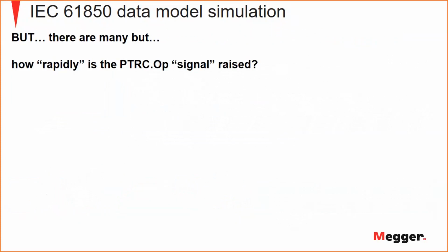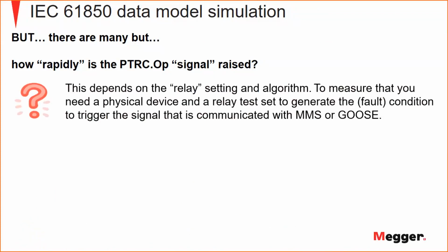But I am a relay protection engineer and I have some issues here. I have my relay protection, I have my settings of my timers, I have my configuration. The relay can be blocked, it can be unblocked, it can be accelerated by carrier send, carrier receive signals, whatever. So I want to see that, and this cannot be done. How fast is a PTRC op signal, so the trip signal, raised? This depends, of course, on the relay setting and the relay algorithm, as I said to you. So the fact that out of that signal we generate a GOOSE message is very important, but it's not the main purpose that I have when I am a relay protection engineer. I have to make sure that that signal comes within 20, 25 milliseconds from the fault inception, or after 4 seconds, if this is my timer.